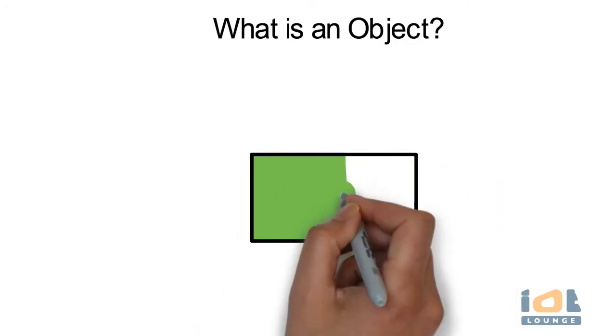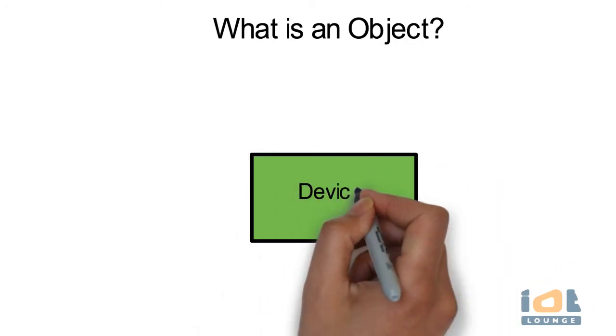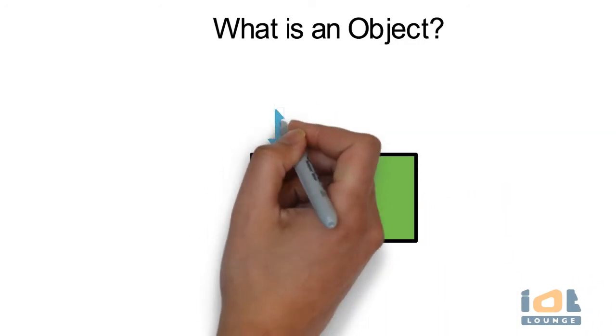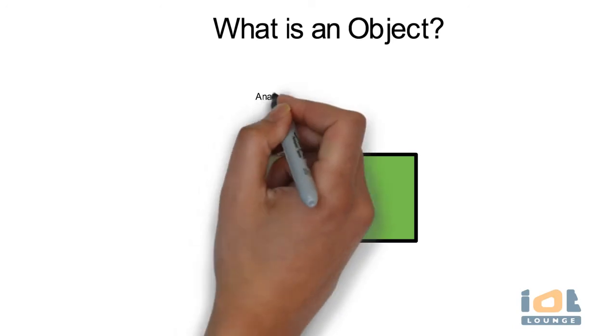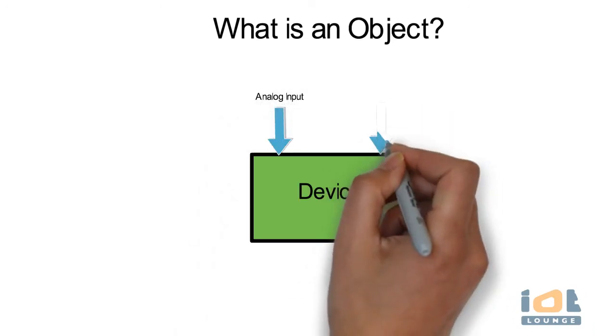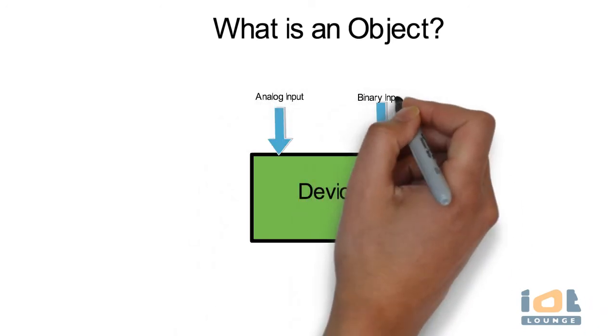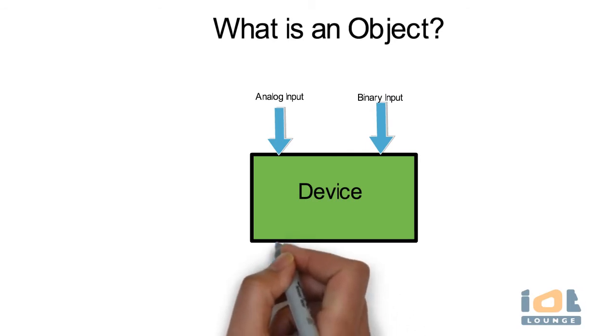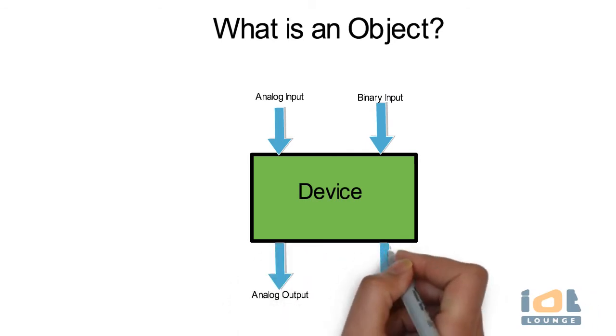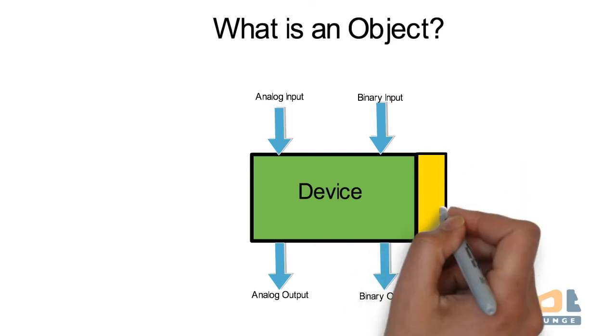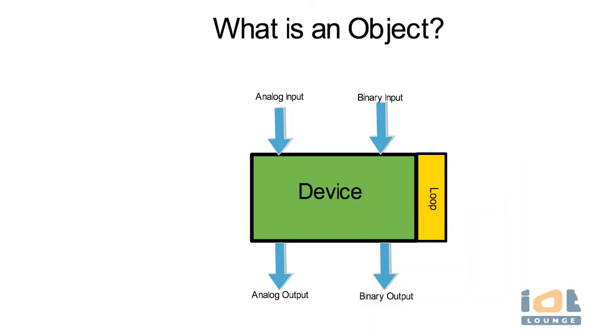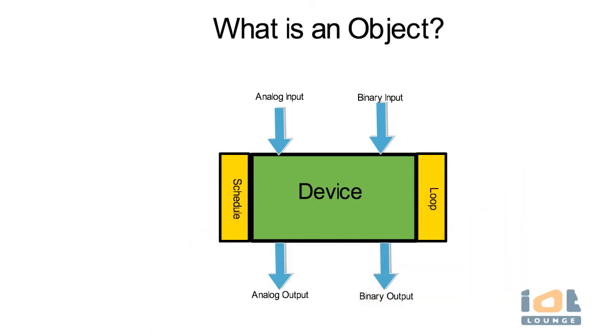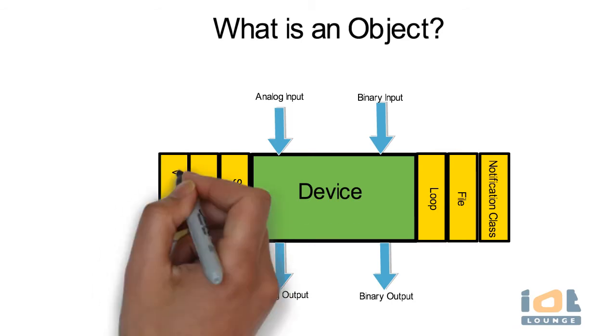What is an object? An object is a collection of information related to particular function. All information is presented in a data structure and each object is represented with multiple properties. The objects may represent physical point or non-physical logical grouping of points. Examples of physical objects include analog input, analog output, binary input, binary output and logical objects include loop, schedule, trend log, device, file, notification class and event enrollment.